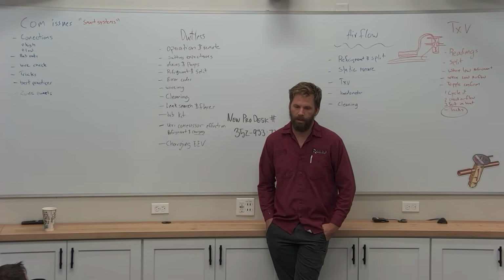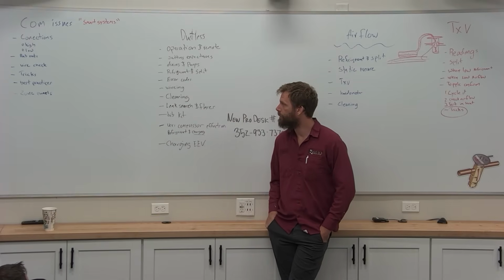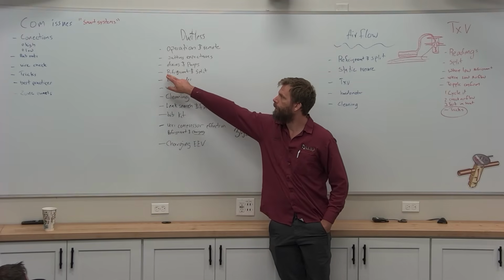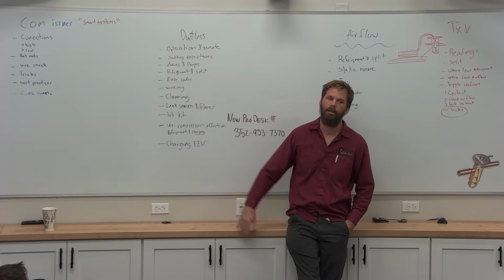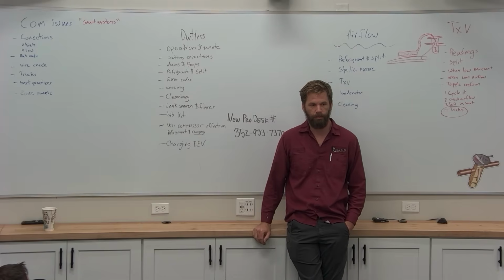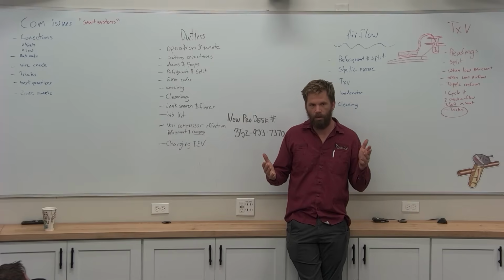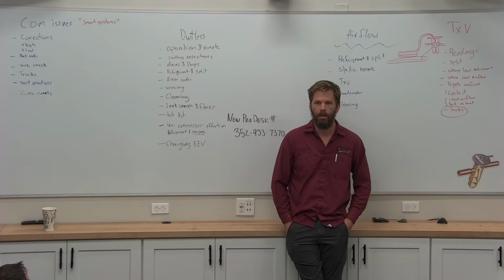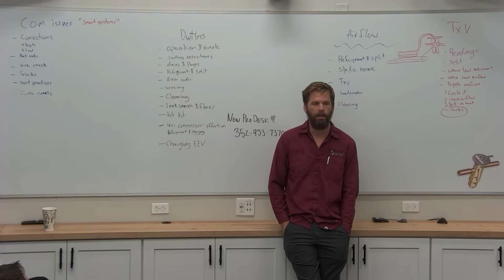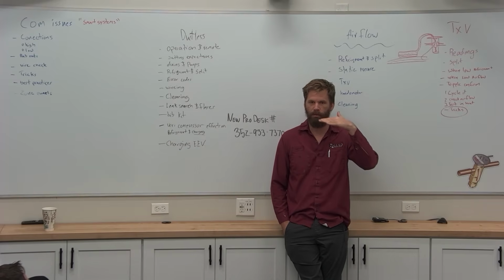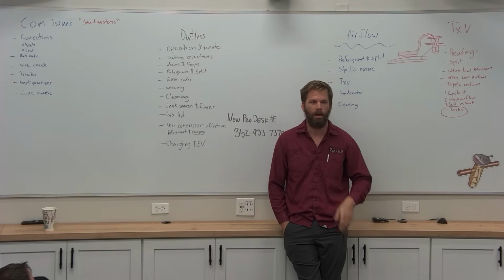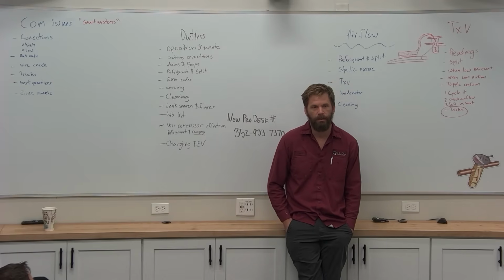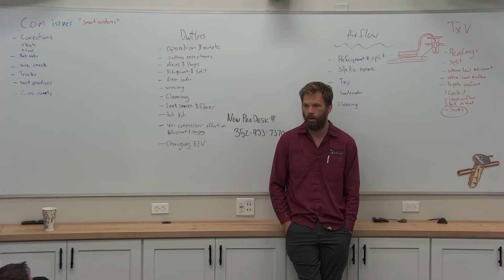Another issue is that technicians are used to charging normal split systems, but the refrigerant and split look a little bit different on your ductless systems. The refrigerant levels are lower. So you'll have a system running full stage, and it might be 119 PSI, and you're like 35, 34 saturation. You could be as low as 32 saturation, where that coil's right on the edge of freezing and everything's running perfect. 109 PSI on your suction and everything is perfect.